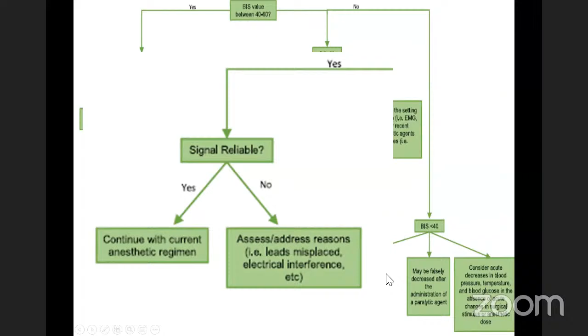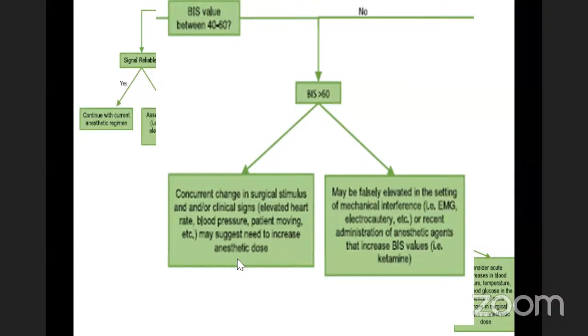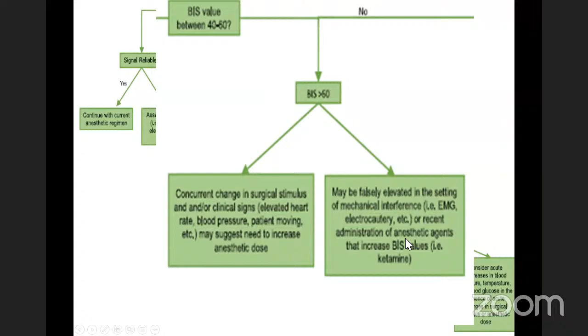Then if the BIS is more than 60, that is, the anesthesia is inadequate. Then we have to look for the factors, that is a concurrent change in surgical stimulus, which warrants a deepening of the plane, or clinical signs which show that the patient needs an increased anesthetic dose, or it may be falsely elevated in the setting of mechanical interference or recent administration of an anesthetic agent like ketamine, which is known to increase the BIS. Now, when the BIS is less than 40, that is a very deep plane.